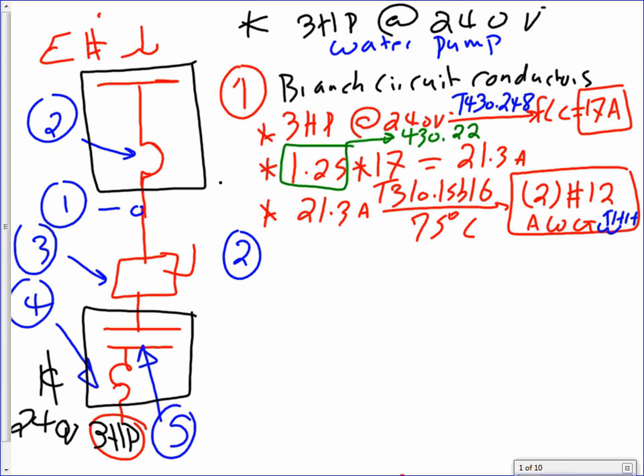Typically, for this size with 2 conductors, the smallest conduit, I can tell you right now, is half an inch. You can't go lower than half an inch anyway. So half-inch PVC conduit, pull it all the way to the water pump, put the conductors in it, and tie them to the other end. Okay. Number 2, the overcurrent protection device.